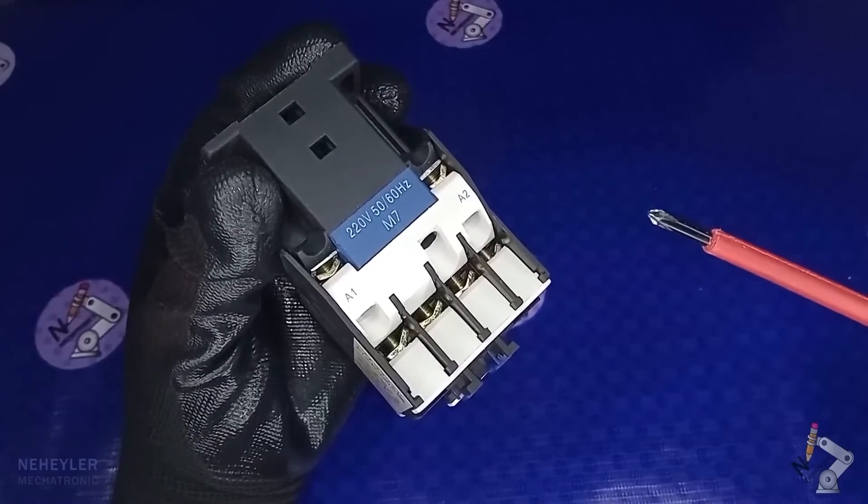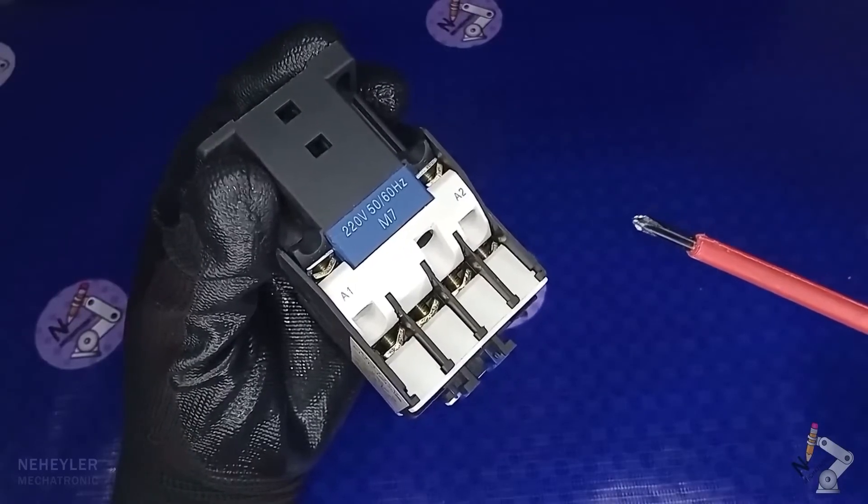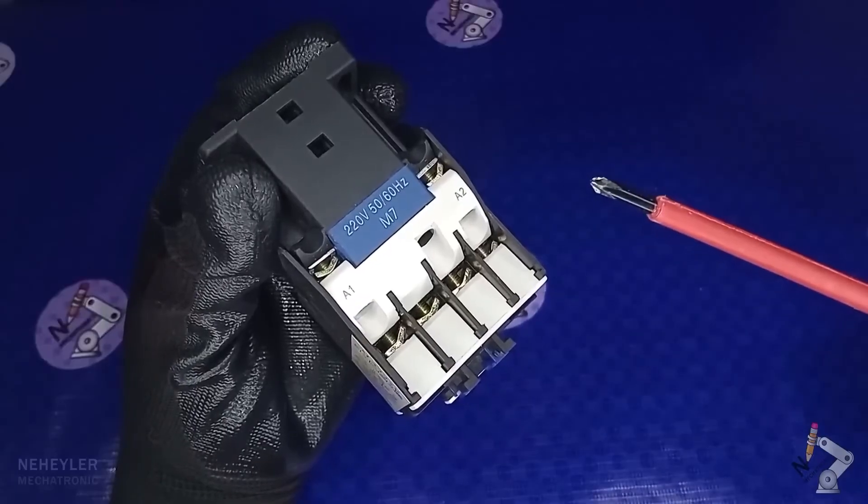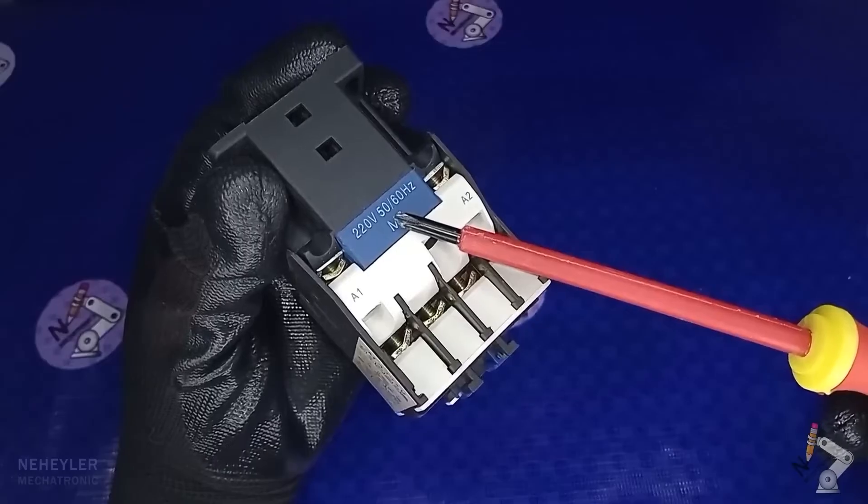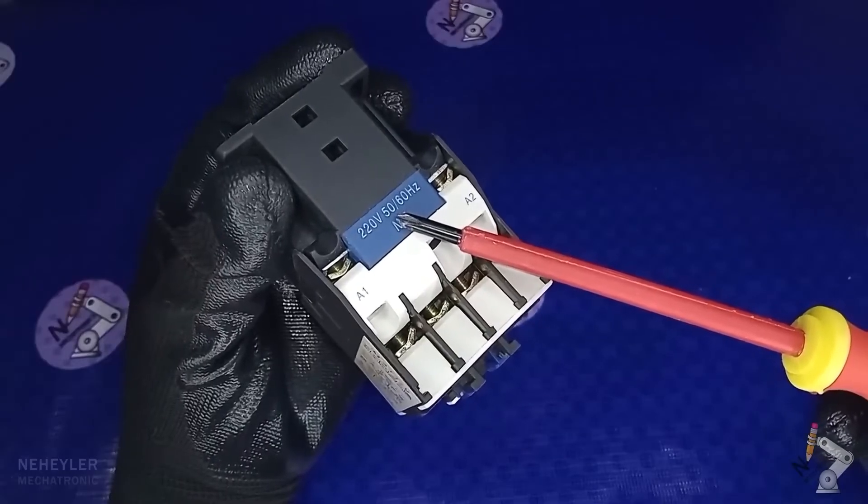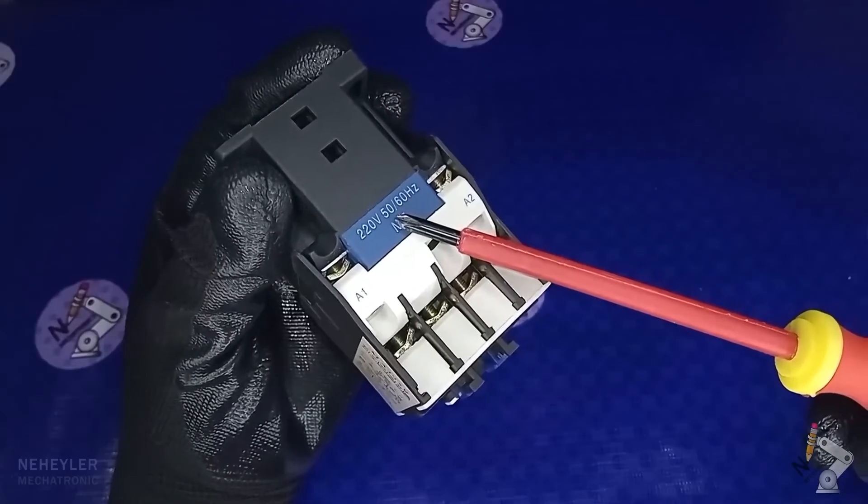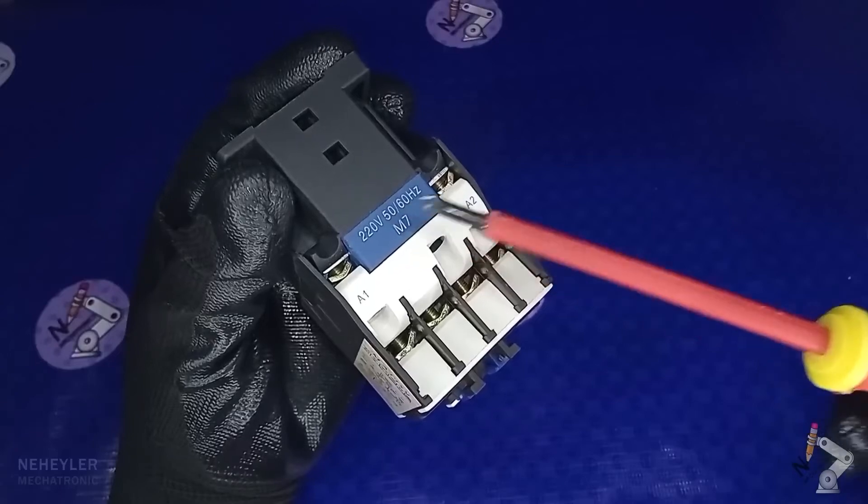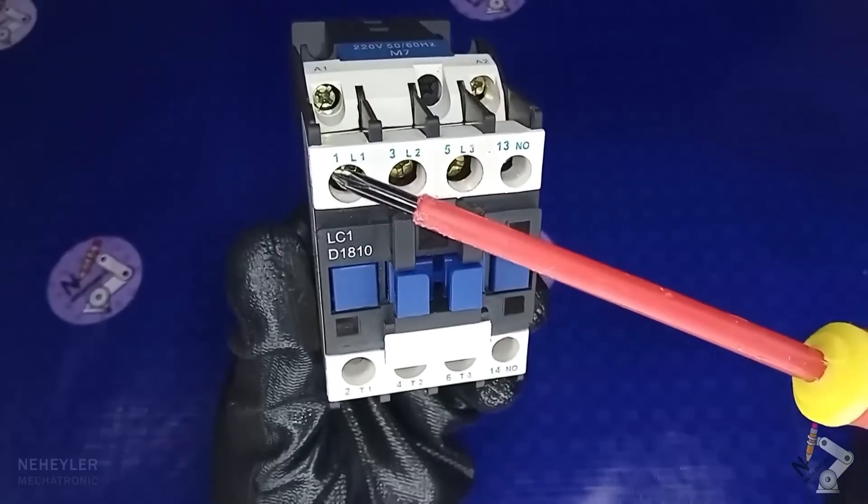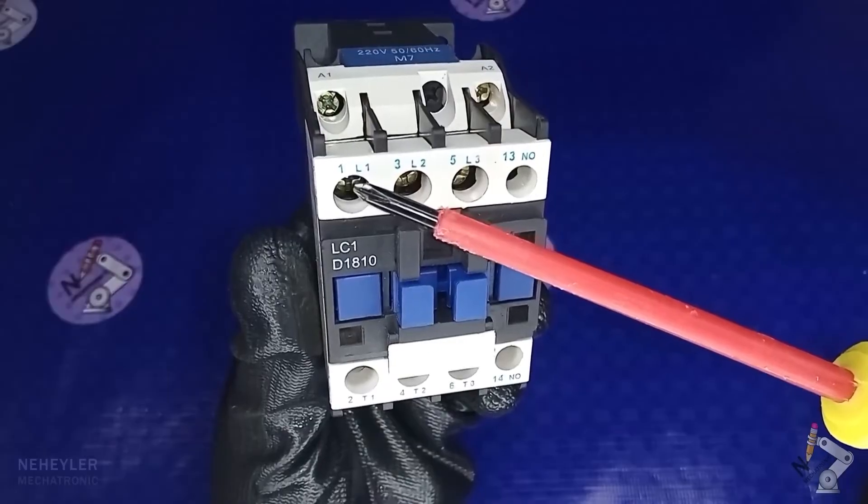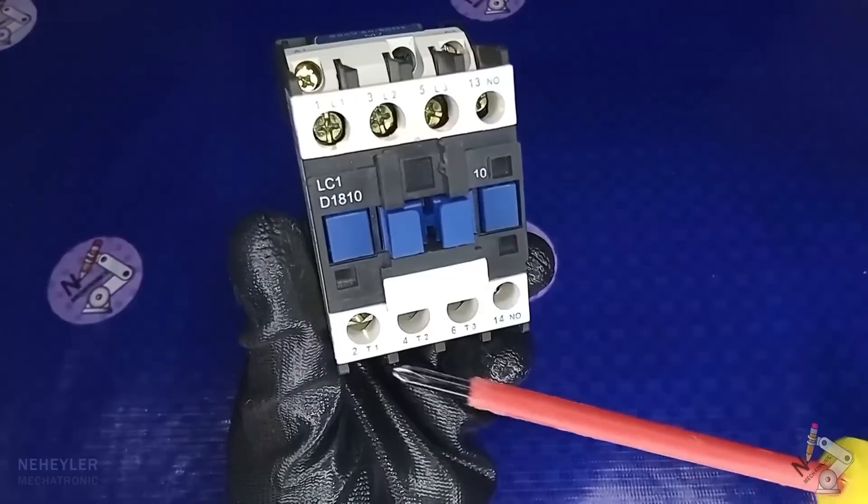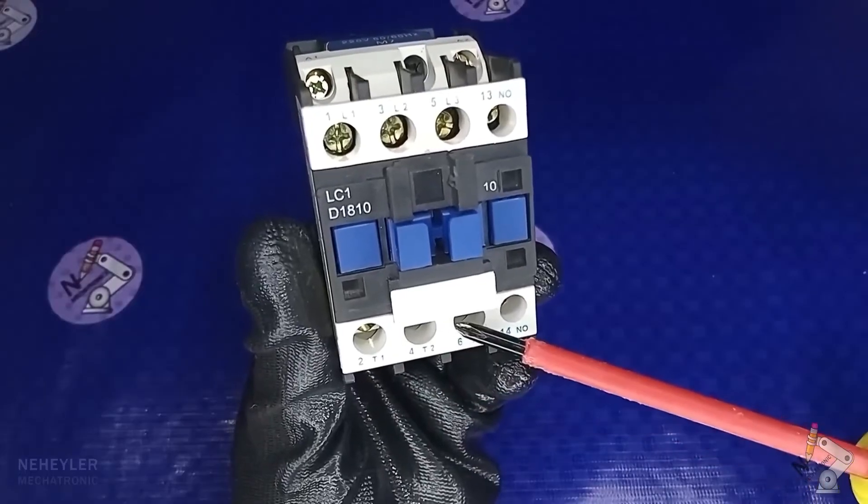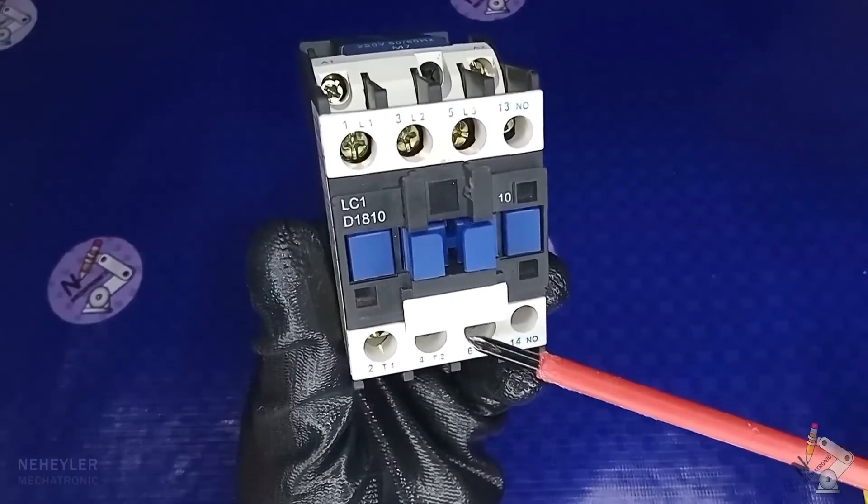That is, between A1 and A2 it must be connected to 220 volts alternating current. In other cases, the coil is powered with 24 volts, 110 volts or any other voltage which will be specified on the device and must be taken into account. On the front we have the main contacts, L1, L2 and L3, which are the input lines. And T1, T2 and T3, which are the work outputs.